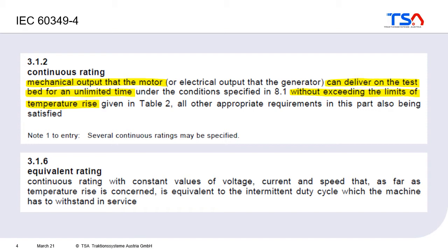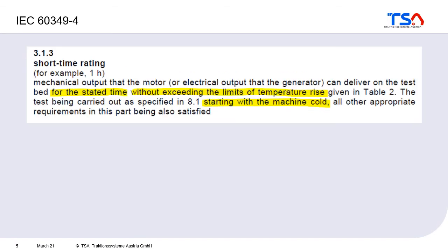How is this checked? It is mostly about the temperature in the machine — if the machine gets too hot, it is definitely not okay, so the motor must stay within the specified temperature limits. Sometimes the continuous rating may not be enough, and you may want to specify a short-time rating — for example, the power at which you can use the machine for one hour without exceeding temperature rise limits. This is checked by starting the machine in cold condition, running it for one hour, and verifying that temperatures remain acceptable.